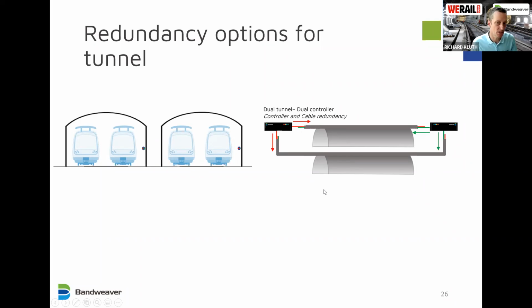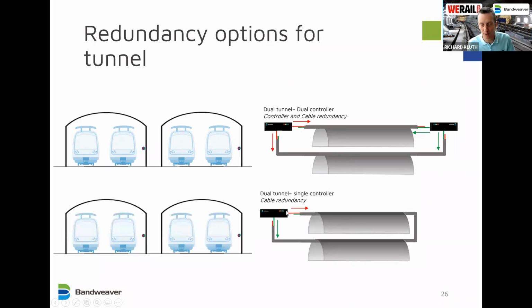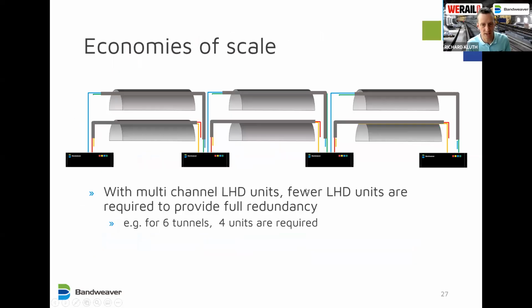As I said, in some cases, customers only want the cable cut redundancy, not the controller. So if we move to a loop configuration, for example here, 1 controller can provide the cable cut redundancy for 2 tunnels. And a cut anywhere would mean you could measure from both sides. So there's real versatility and flexibility.